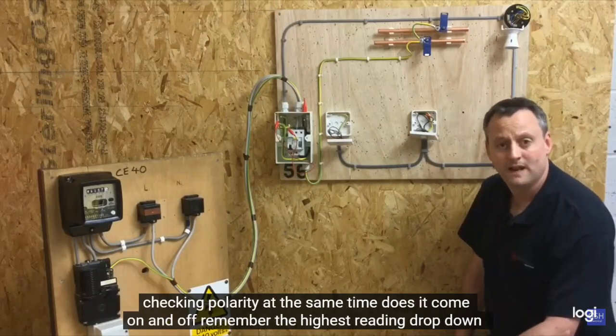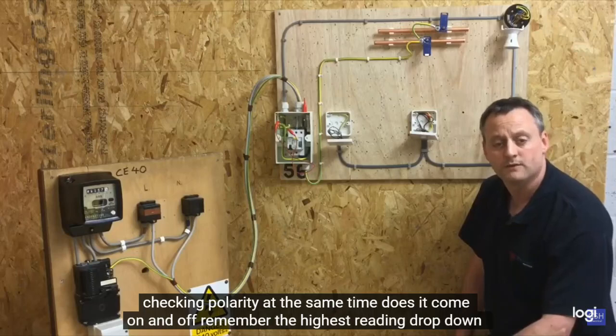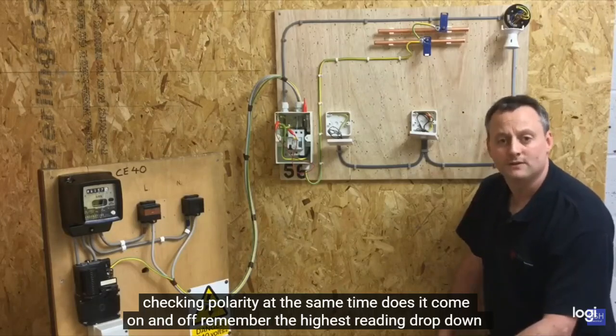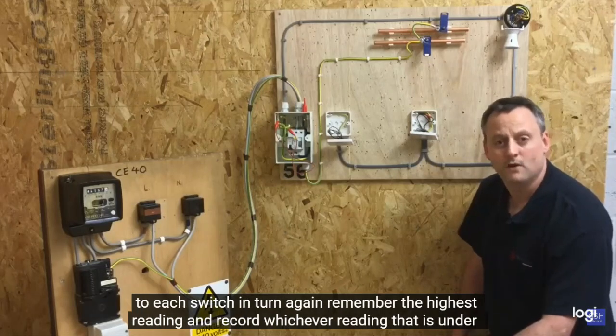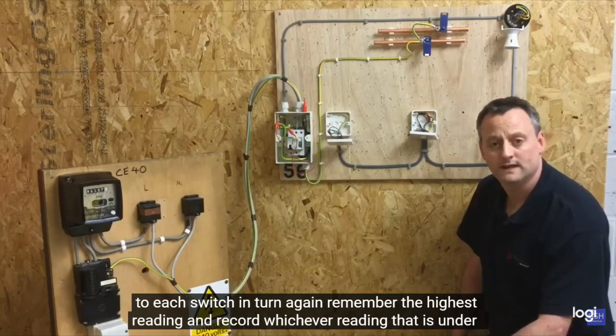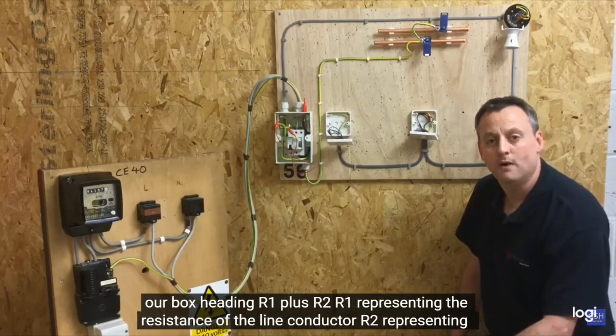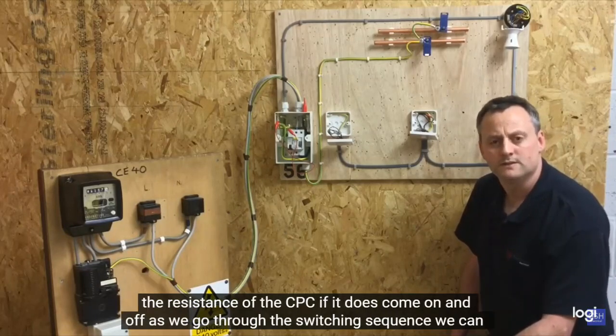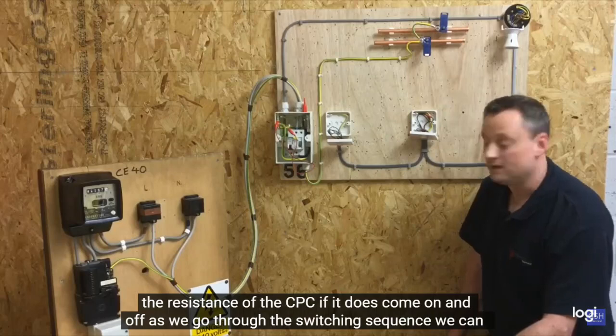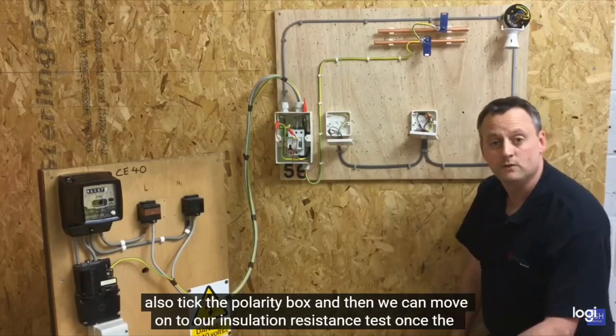Under our box heading R1 plus R2, R1 representing the resistance of the line conductor, R2 representing the resistance of the CPC. If it does come on and off as we go through the switching sequence, we can also tick the polarity box, and then we can move on to our insulation resistance test once the covers have been reinstalled. So let's get on with the continuity of CPC and polarity combined test next.